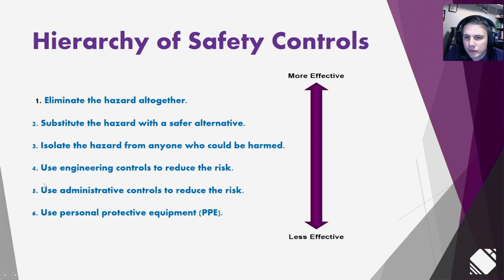Use engineering controls to reduce the risk. That would be something like the Kirk key, or a keyed interlock that I talked about earlier, where somebody cannot operate a device until the power upstream has been disconnected, because that device is not rated to interrupt the power on its own. It's just an isolation method. So there'd be an engineering control that prevents anybody from unsafe behavior.